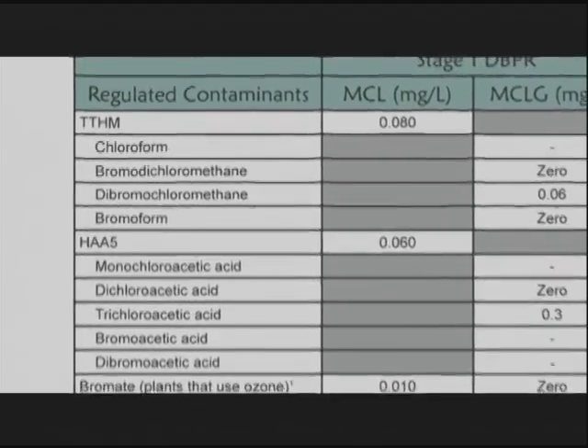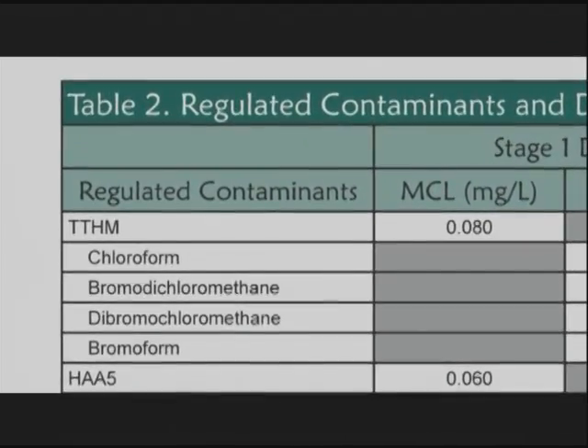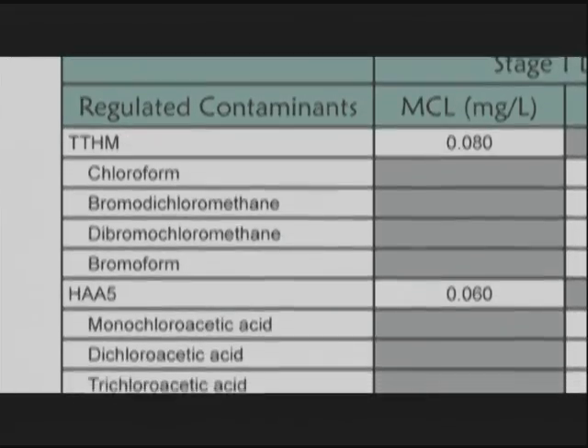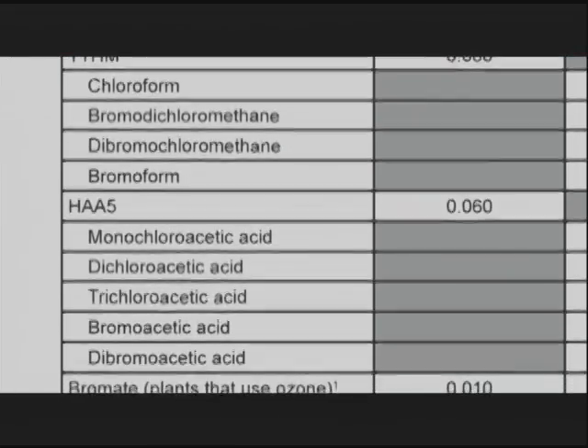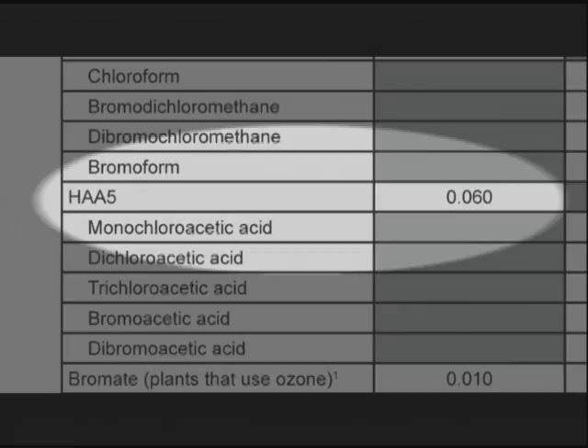The maximum contaminant level, or MCL, for total trihalomethanes is 0.08 milligrams per liter, or 80 parts per billion. The MCL for all five haloacetic acids is 0.06 milligrams per liter, or 60 parts per billion.